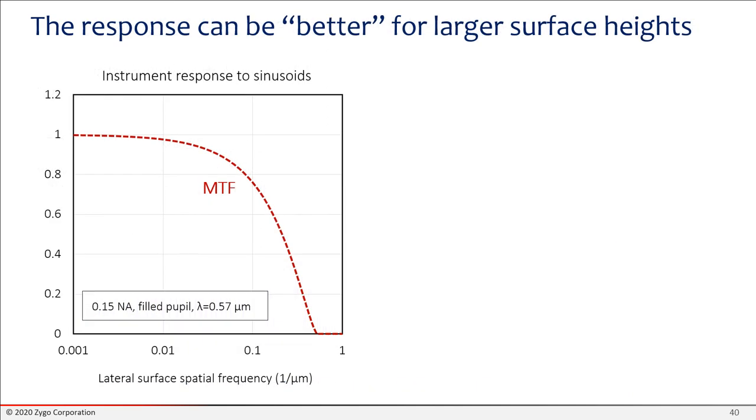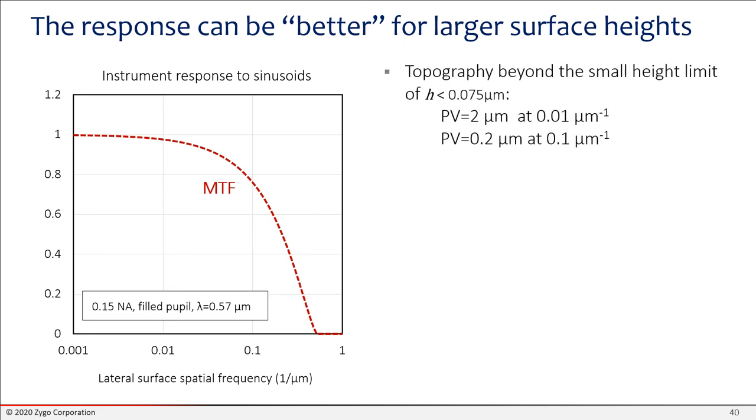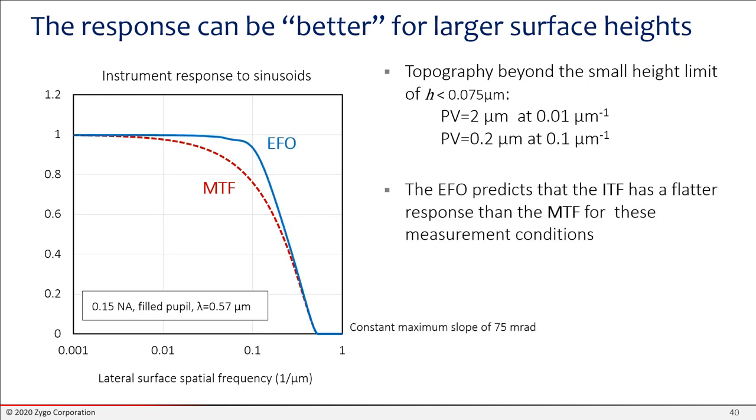For larger surface height variations, larger than this lambda over 8 limit, we find that the response of the instrument varies a little bit. It's no longer following the MTF perfectly. So for example, if we say let's go through a series of sinusoids that meet a slope limit, in other words, the maximum slope on the part is not so large that the light is deflected outside the acceptance of the objective, then you could have a peak valley of up to 2 microns, which is much bigger than the small height limit. And if you calculate using the EFO what the response of the instrument is, curiously enough, you find that it's a bit flatter out to 0.1 inverse microns spatial frequency. I think the key takeaway is that you can calculate this with this model, and that's a useful thing to do, and the calculation is quite quick.